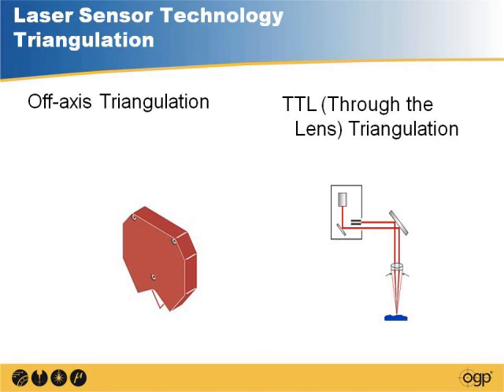The TTL laser on the right stands for through the lens, and it basically sends down that beam through the optical system, the same optical system that's used for video measurement. So there are some advantages to that. You typically get a little bit more working distance, and you also have no offset associated with the video to the laser. So in other words, they're at the same XYZ location when you're measuring features on one part with both sensors. For the off-axis lasers, we calibrate that offset out because you have the optical path at one location and the laser path at another location, and as long as we know that offset, we can calibrate it out and maintain a coordinate system on a single part.